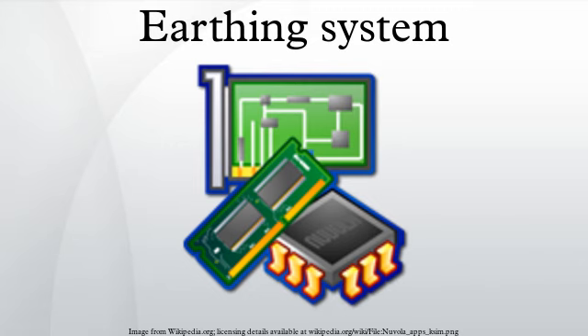Properties. Cost. TN networks save the cost of a low-impedance earth connection at the site of each consumer. Such a connection is required to provide protective earth in IT and TT systems. TN-C networks save the cost of an additional conductor needed for separate N and PE connections. However, to mitigate the risk of broken neutrals, special cable types and lots of connections to earth are needed. TT networks require proper RCD protection.